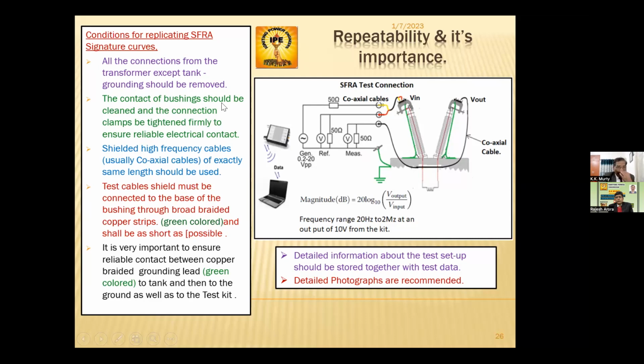The contact of the bushing should be cleaned and the connection clamp tightened firmly to ensure a reliable electrical connection. Shielded high frequency cables, usually coaxial cables of exactly the same length, should be used. The test cable shield must be connected to the base of the bushing through a broad braided copper strip, green colored, and shall be as short as possible.